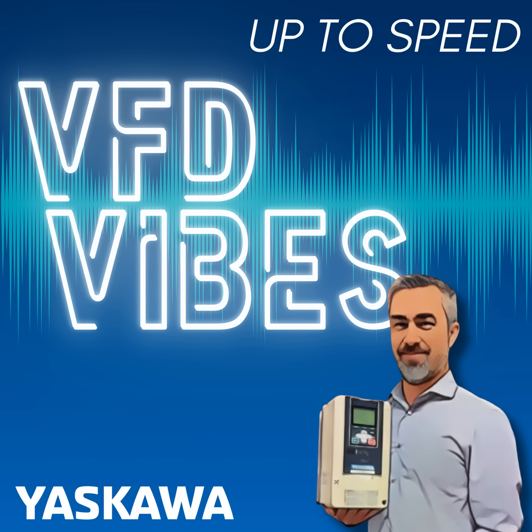Yeah, typically a passive harmonic filter is one-to-one, so you will have one for each drive. And either the filter manufacturer can provide guidelines on drives that they've tested or approved to be used with their filters, or you can also consult with the drive manufacturer and cite the particular filter you're looking to use, and often they can provide some guidance on A, if it'll work, or B, if there's a potential issue, what can be done to make it work.